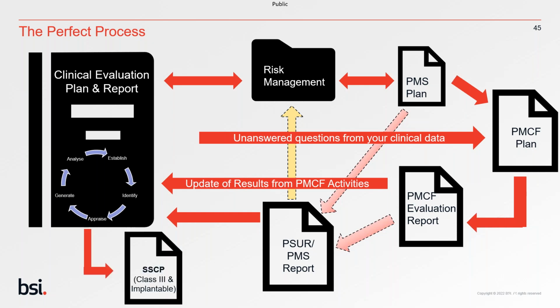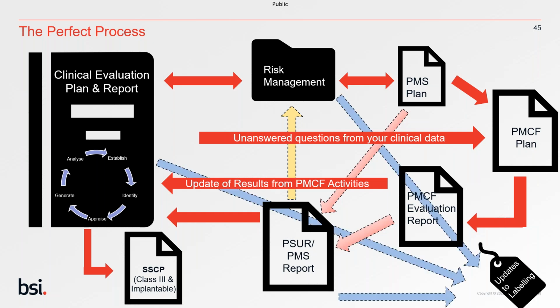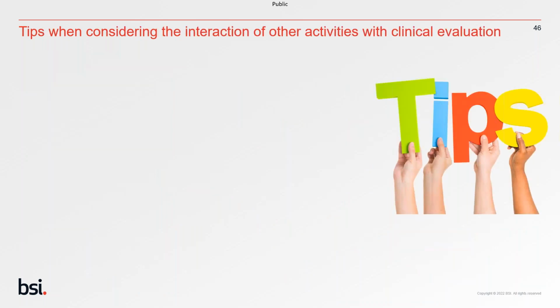And what we get here is obviously whenever you update your clinical evaluation plan for your class 3 and implantable devices, you will need to update your SSCP as well. Anytime you update your clinical evaluation report, really think about the impact that will have, and do you need to communicate that information to your healthcare practitioners or your patients via your SSCP? And without saying, this is the last bit, I promise, but really think about those updates to labeling as well from all of these activities: updates to your clinical evaluation plan, your risk management, and your PSUR and PMS report.